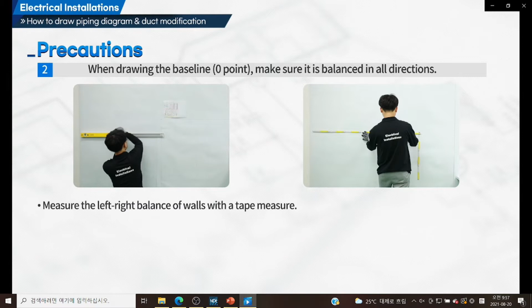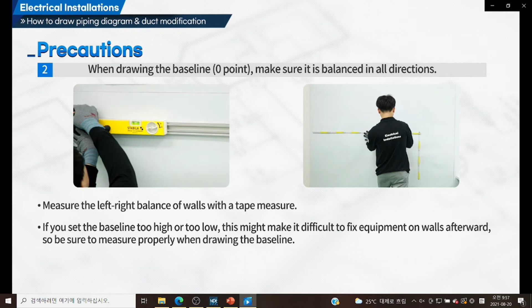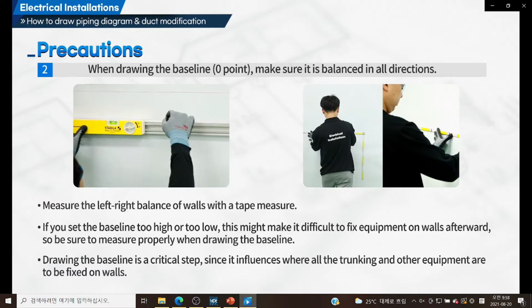Second, when drawing the baseline, the 0 point, make sure it is balanced in all directions, measuring the right-left balance of walls with a tape measure. If you set the baseline too high or too low, this might make it difficult to fix equipment on walls afterward. So be sure to measure properly when drawing the baseline, since it is a critical step influencing where all the trunking and other equipment are to be fixed on walls. Third, when cutting ducts, check whether the cutting direction corresponds with the layout.